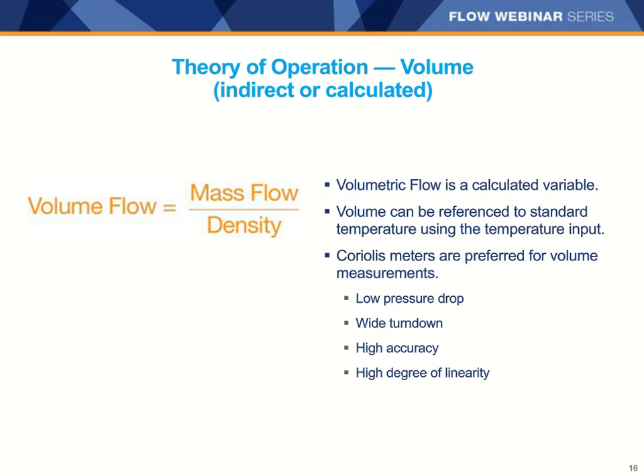Volumetric flow is a calculated variable derived by dividing the mass flow reading by the density of the fluid. The resulting measurement is very accurate and can be referenced to standard temperature using the secondary temperature measurement of the sensor. Examples of other benefits of using Coriolis meters to measure volumetric flow: a low pressure drop, wide turndown, high accuracy, and a high degree of linearity.